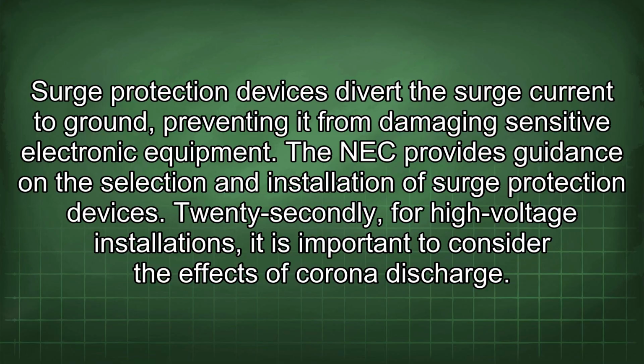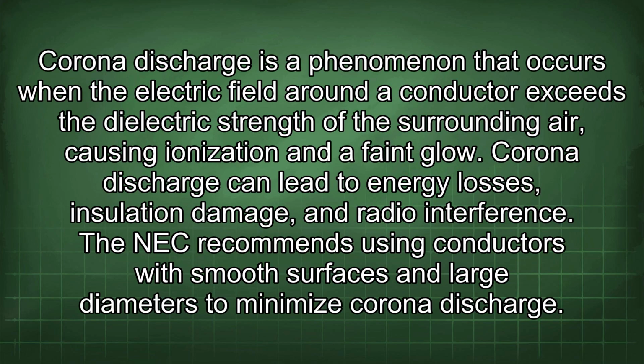22nd, for high voltage installations, it is important to consider the effects of corona discharge. Corona discharge is a phenomenon that occurs when the electric field around a conductor exceeds the dielectric strength of the surrounding air, causing ionization and a faint glow. Corona discharge can lead to energy losses, insulation damage, and radio interference. The NEC recommends using conductors with smooth surfaces and large diameters to minimize corona discharge.